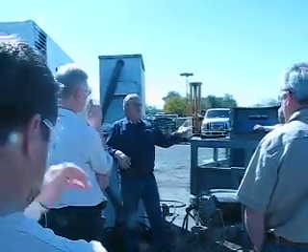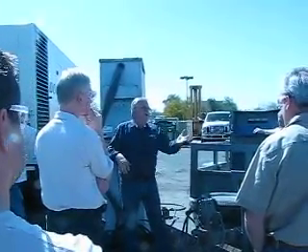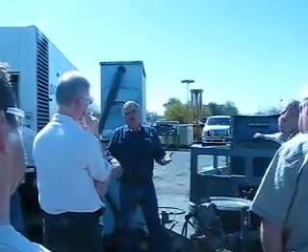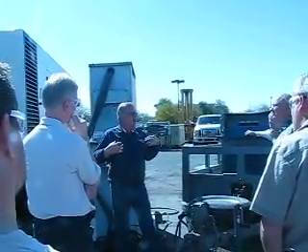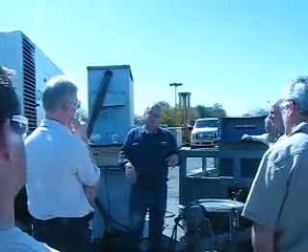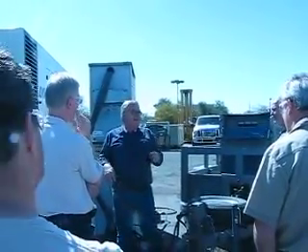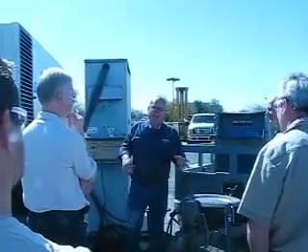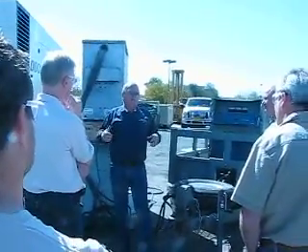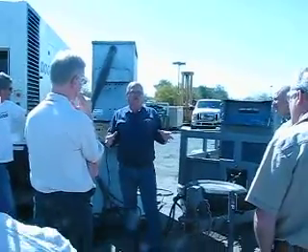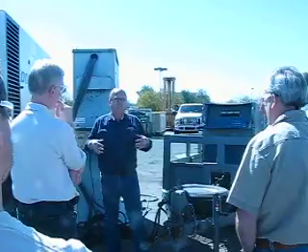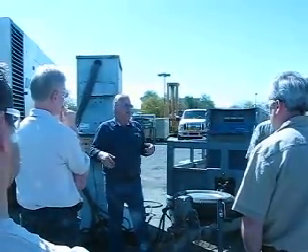So, you know, how many people ask for a reactive load bank? Nobody. I can tell you, if you want me to do a reactive load bank, I'm going to do cartwheels down the parking lot, because that's good money. Okay? You charge for that. These things are expensive. So, you know, I love doing reactive load banking, but the reality of it is most people on an annual service really don't need reactive load banking.